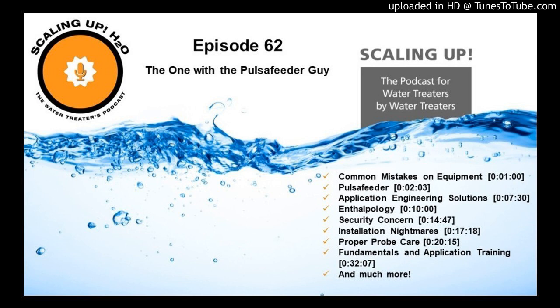How often, if everything is correct, should we expect to replace those probes? So manufacturers of the probes say that sitting on a shelf in buffer solution, the shelf life is 2 years. I've seen someone get away with using a probe for 3 or 4 years. I guess my rebuttal is, how precise do you want to be with the probe? If half a pH is good enough, then the replacement time can stretch a little bit. If you need it precise within 0.2 pH, then your change frequency should be higher. I'd recommend an annual switch out. I mean, your system's being turned off.